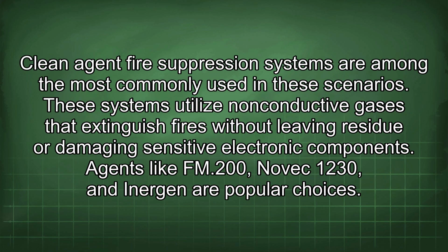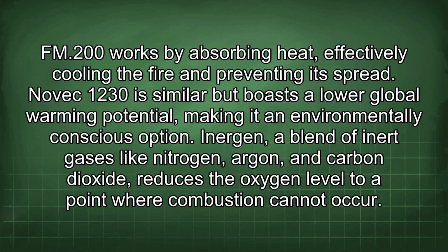Clean agent fire suppression systems are among the most commonly used in these scenarios. These systems utilize non-conductive gases that extinguish fires without leaving residue or damaging sensitive electronic components. Agents like FM200, Novec 1230, and Inergen are popular choices. FM200 works by absorbing heat, effectively cooling the fire and preventing its spread. Novec 1230 is similar but boasts a low global warming potential, making it an environmentally conscious option.